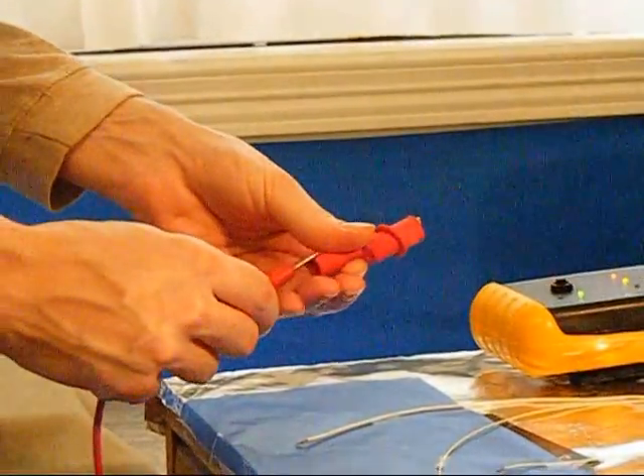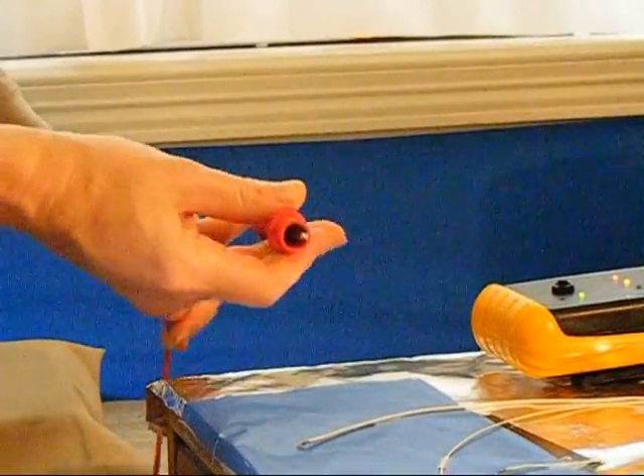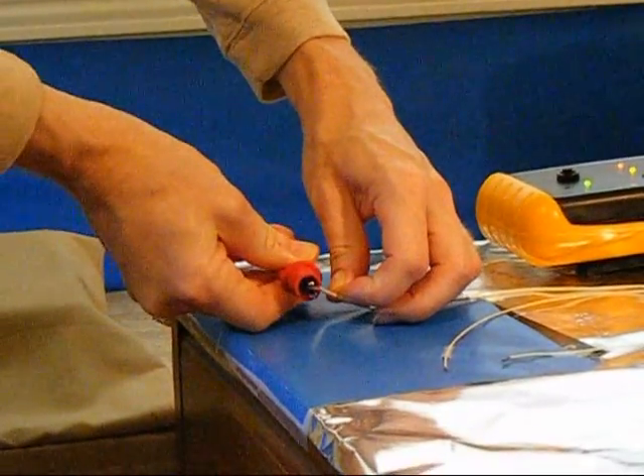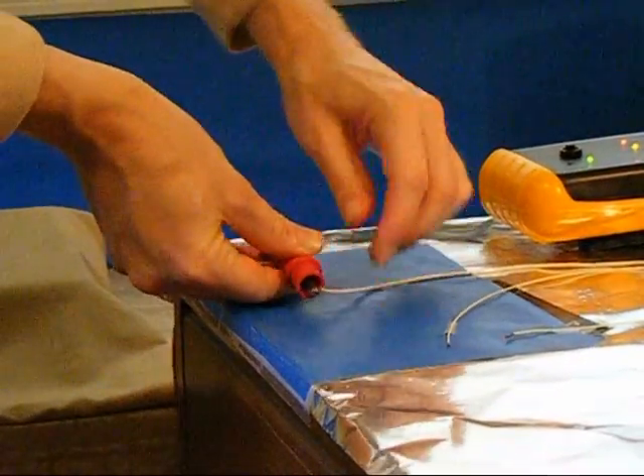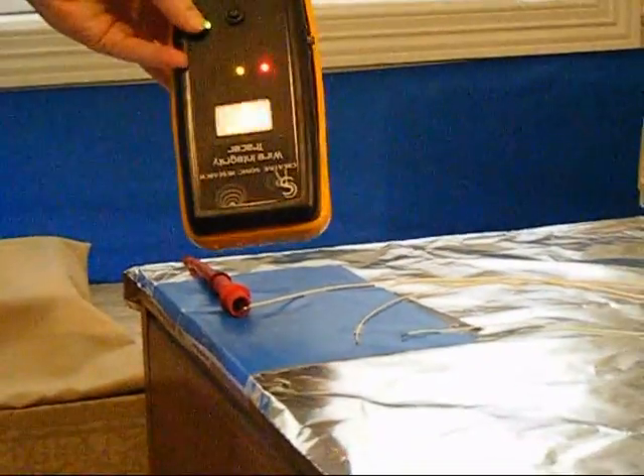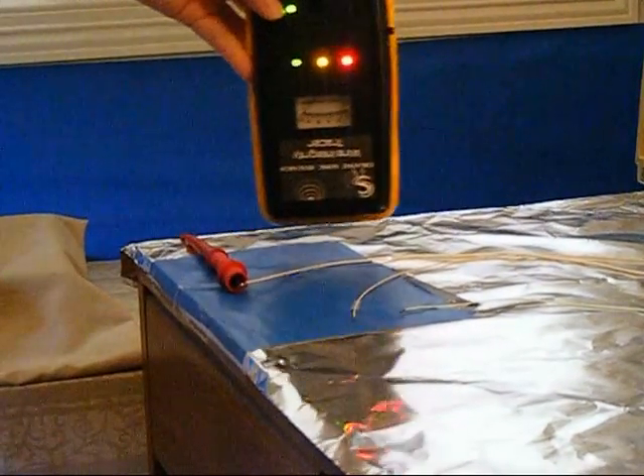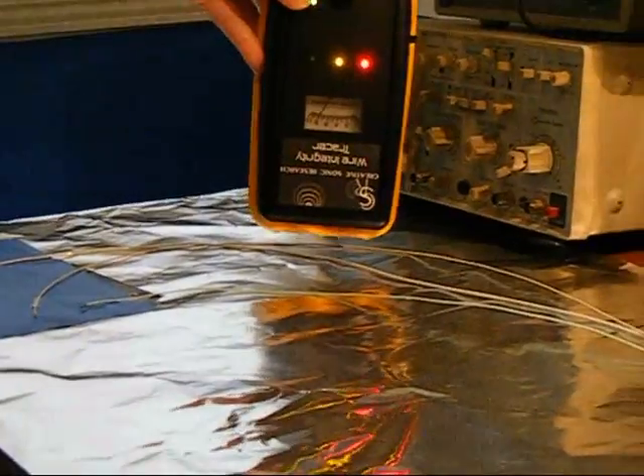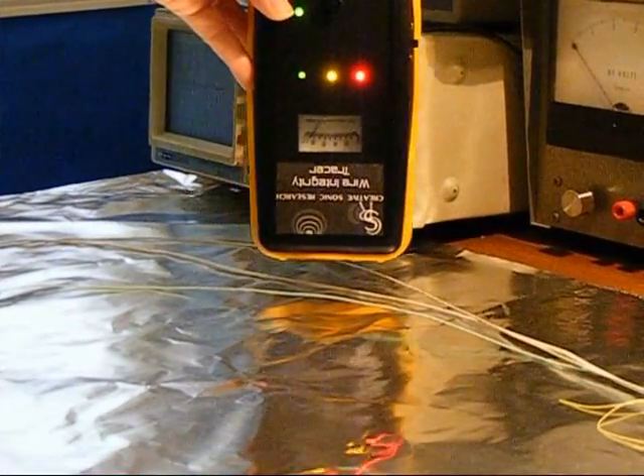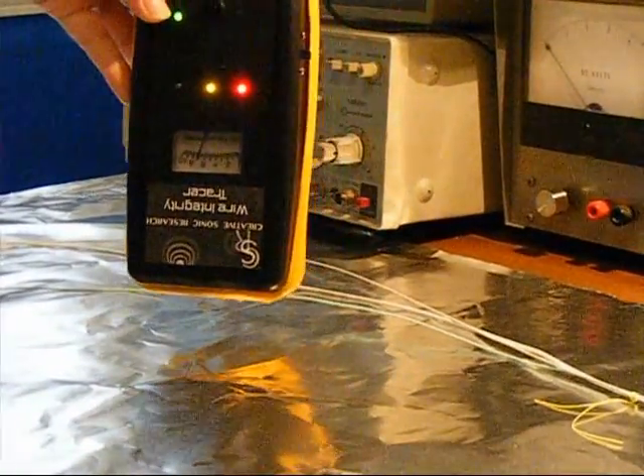Now you will see how we use our WITS to locate exactly where along the wire it contacts ground. Detect and locate. We connect the transmitter output lead to the shorted wire and then use the tracer to follow the reference signal along the shorted wire's path. We ensure we are tracing only the wire's path by observing either the tracer's meter reading or by watching the tracer's LED level indicators as we move the tracer.